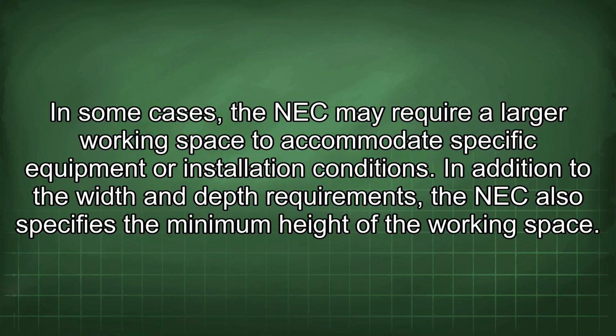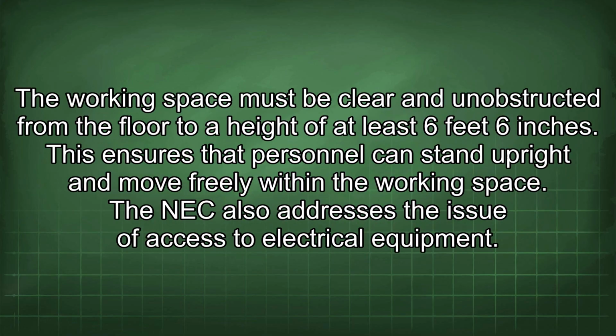In addition to the width and depth requirements, the NEC also specifies the minimum height of the working space. The working space must be clear and unobstructed from the floor to a height of at least 6 feet 6 inches. This ensures that personnel can stand upright and move freely within the working space.